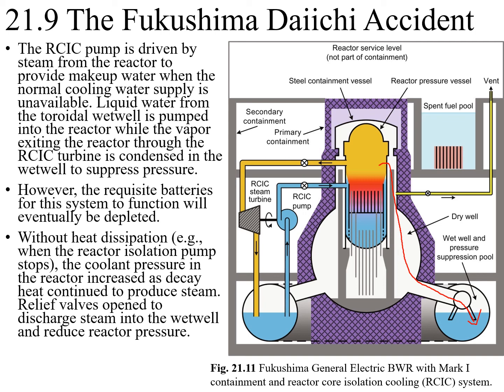Units 2 and 3 featured a reactor core isolation cooling system, the RCIC system. This RCIC pump is driven by steam from the reactor to provide makeup water when the normal cooling water supply is unavailable. You can see that this system is designed in this way. You have the steam produced from the core. This steam is used to rotate a small turbine. Then the exhaust steam is sent to the suppression pool for condensing. This rotation also drives a pump. This pump takes the water from the suppression pool and sends it back to the core for continuous cooling.